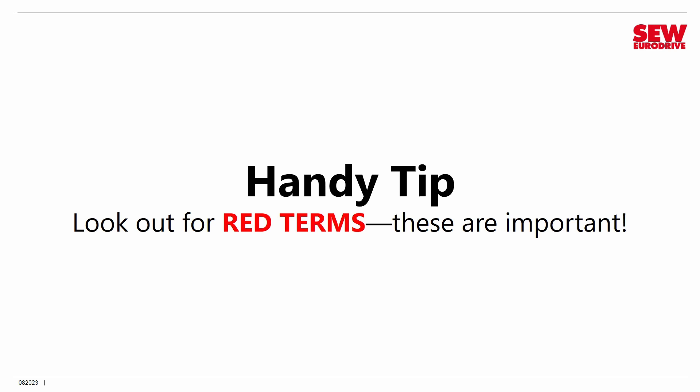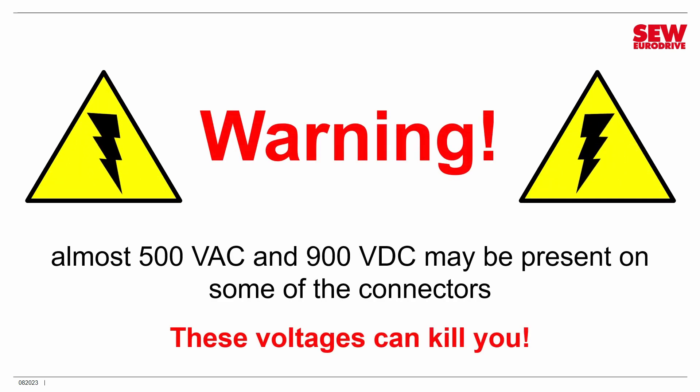One warning: the equipment we're working with is definitely not a toy. We are working with sophisticated industrial equipment that operates on fairly high voltages. Some models of the MOVITRAC LTE-B+ operate on almost 500 volts AC, and some connectors have up to 900 volts DC on them. These voltages are serious — they can kill you, injure you, or burn you. So be safe. I recommend a cutoff switch of some kind on your VFD so it can be switched off quickly. If you follow standard electrical safety, you should be just fine.